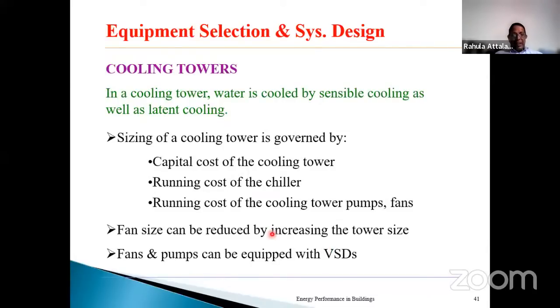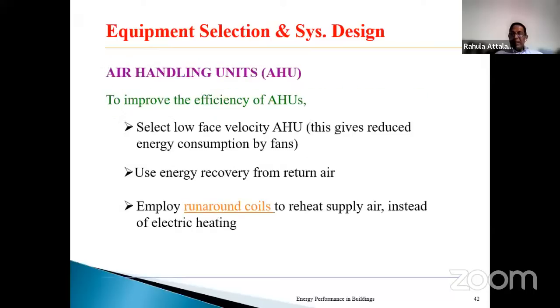Cooling towers, instead of operating at constant speed, can be accommodated with VSDs depending on the load variation. Same with the air handling unit. To change the flow rate of the air handling unit, you can have the VSD based on the load, and also have the energy recovery unit, because the air handling unit will have return air coming from the space, which is cold air that can be recovered. That coldness can be recovered to the incoming air through a suitable heat recovery system.